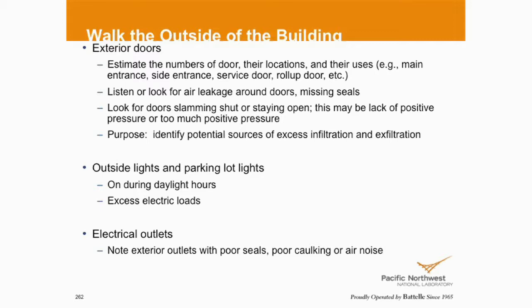Outside lights, are they on during daylight hours? Again, that's an opportunity. Parking lot lights, possibly another opportunity. A lot of vendors now have solutions for parking lots. It's not cheap, but it's something to be aware of. Outlets, are they sealed? Honestly, I don't spend a lot of time looking at outlets. Expansion joints on buildings. Again, college campuses, a lot of buildings have expansion joints. We found one building where all the caulking, or whatever the material was in the expansion joint, was gone. The building was negative, so it was sucking it right in.